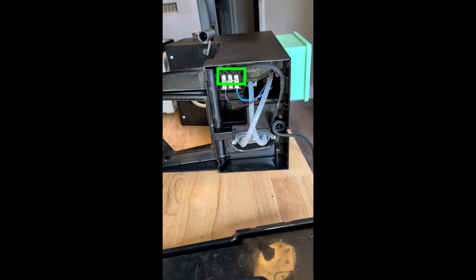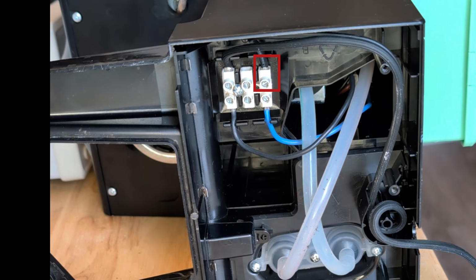Unscrew the old cable from the connector block. Screw the live wire of the new power cord to the live side of the power block, aka the blue cable. Screw the neutral end of the power cord to the neutral end of the connector block. The grounded cable can now be installed in the center connection point of this connector block. Make sure all wires are firmly connected.